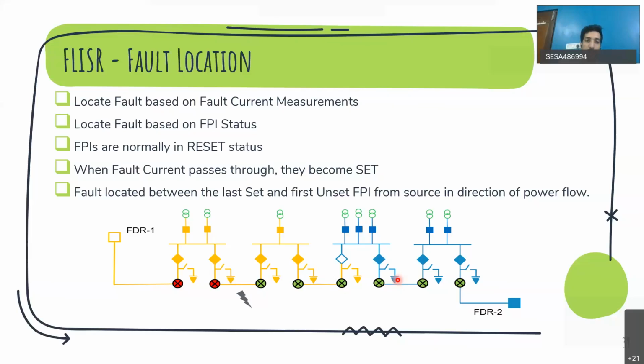So we are seeing different stages of FLISR. First stage is fault location. The fault will be located based on two ways, one is based on the fault current measurements.